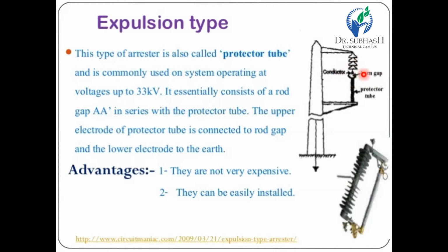In this figure, we can see the rod gap or horn gap, and this black part is the protector tube, and these two are in series. The upper electrode of the protector tube is connected to the rod gap, and the lower electrode is connected to earth. So the lower electrode, this one, is connected to ground. Now the advantages: they are not very expensive and they can be easily installed. So these are the advantages of the expulsion type lightning arrestor. This one is the image of a typical expulsion type lightning arrestor.